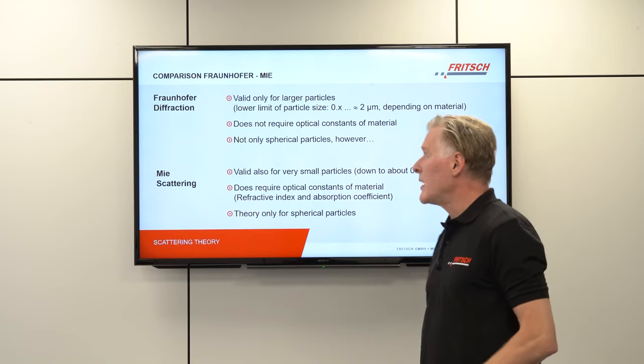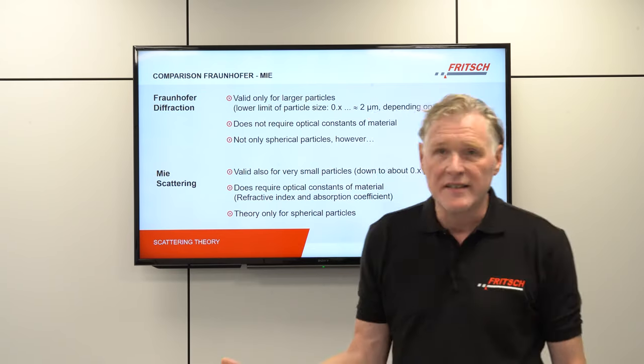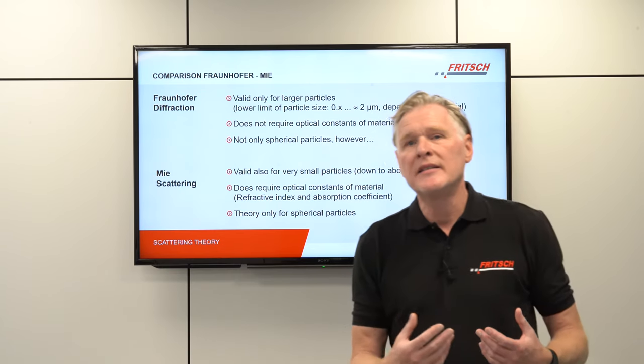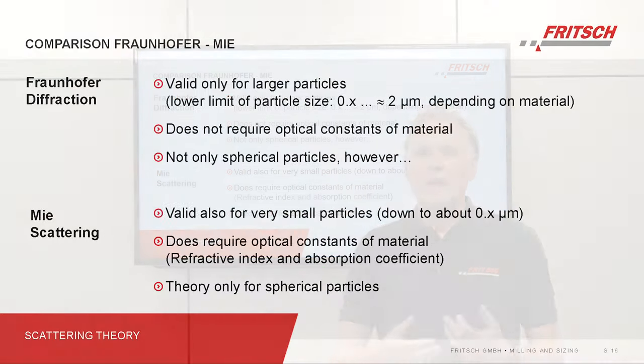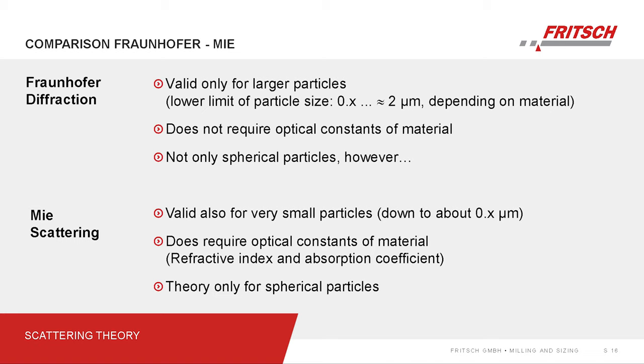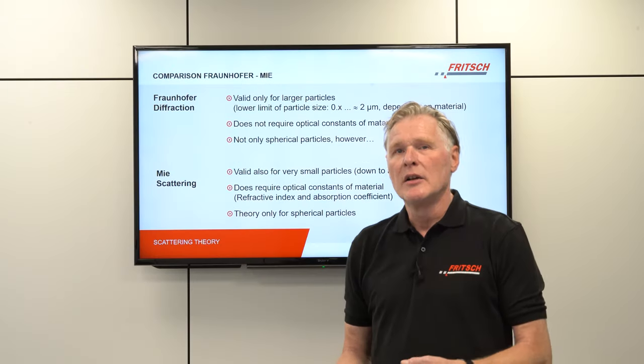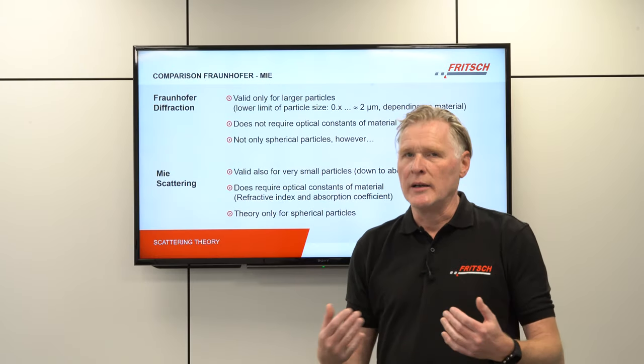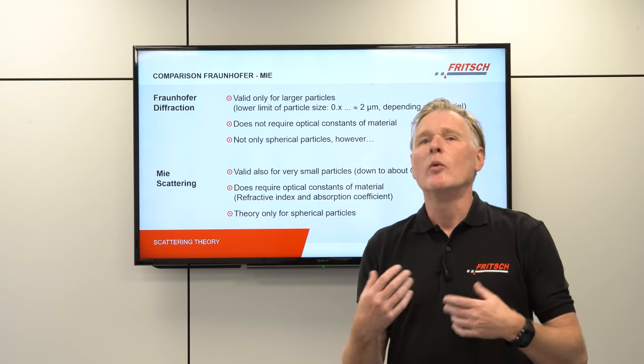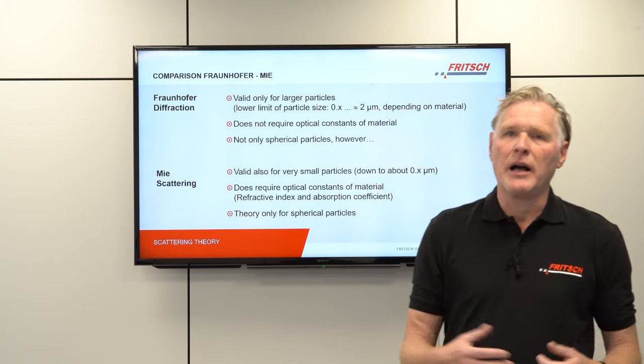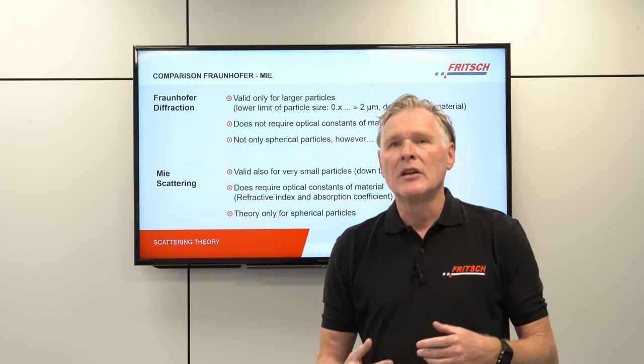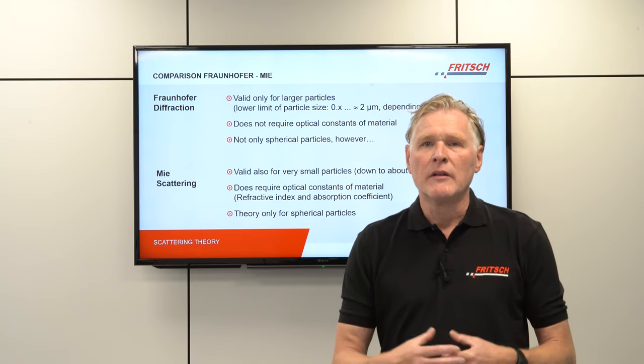Fraunhofer diffraction is valid for large particles — meaning the diameter of the particles must be larger than the wavelength of the light used in the instrument. With our instrument, for example, we have a green laser with a wavelength of around half a micron. So above around two to three microns — which also depends on the material being measured — you get reliable results from Fraunhofer diffraction.